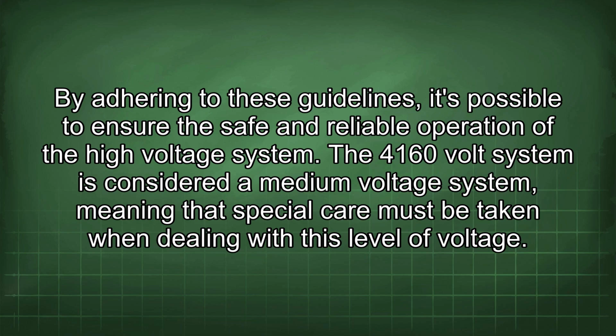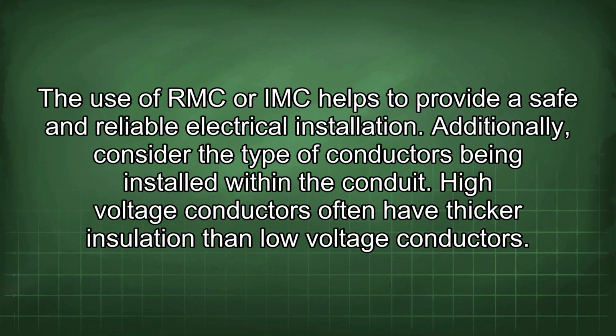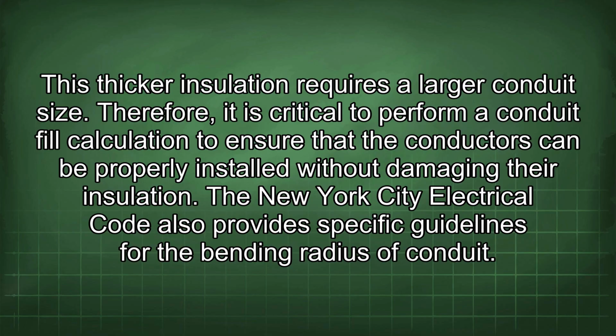A 4160-volt system is considered a medium-voltage system, meaning that special care must be taken when dealing with this level of voltage. The use of RMC or IMC helps to provide a safe and reliable electrical installation. Additionally, consider the type of conductors being installed within the conduit. High-voltage conductors often have thicker insulation than low-voltage conductors. This thicker insulation requires a larger conduit size.